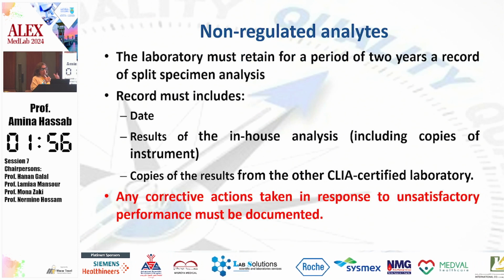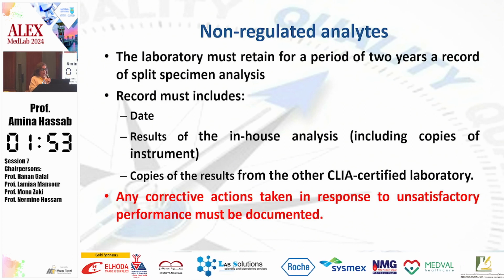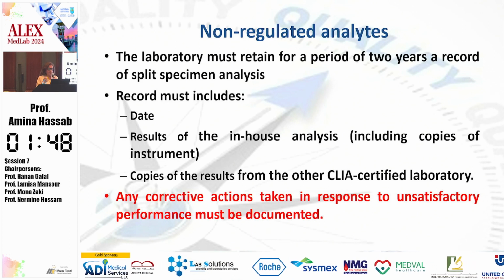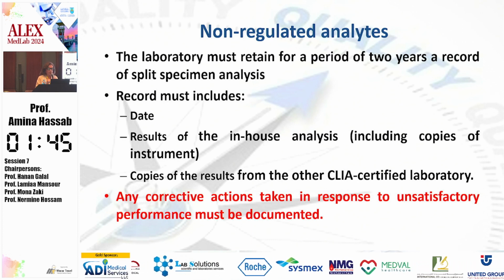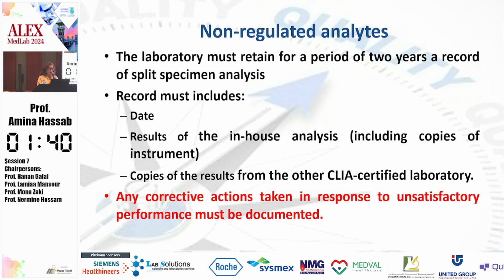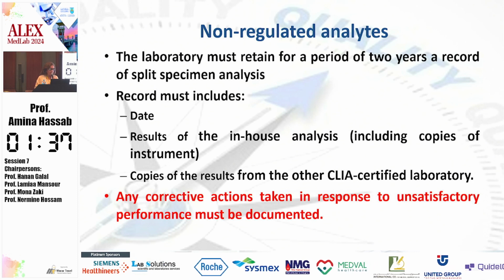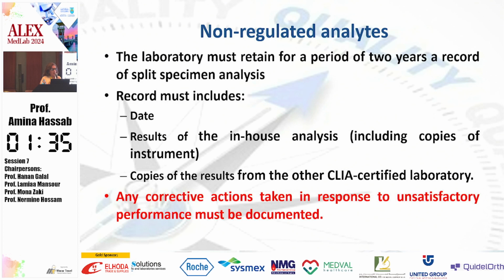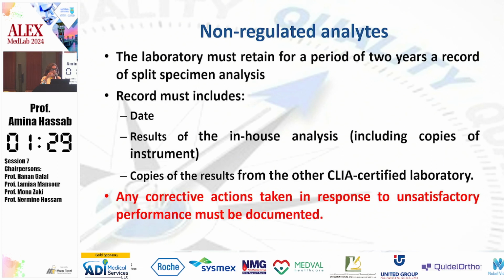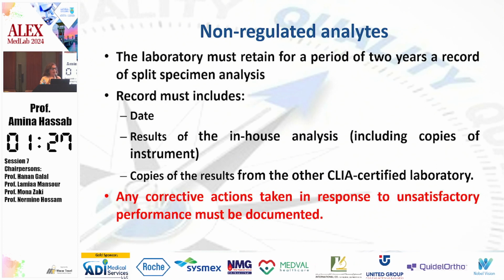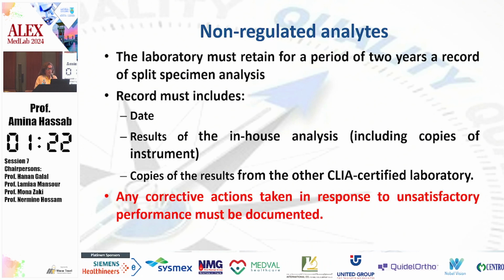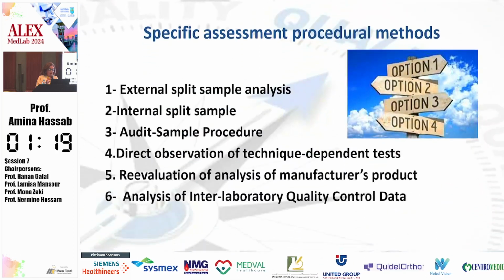So after I do my comparison with the referral lab that I choose, we have to document our data and keep the records for 2 years. Actually, all I'm talking about is the CLIA regulation for alternative assessment and CAP regulation. So we have to record the date where we did this assessment and the results of the in-house, and also keep the printout of the analyzers. Any corrective actions, of course, must be investigated and documented.